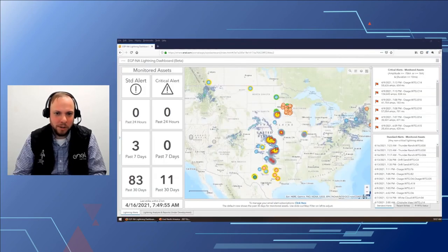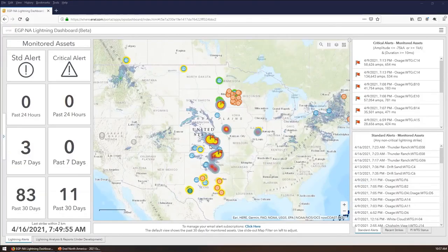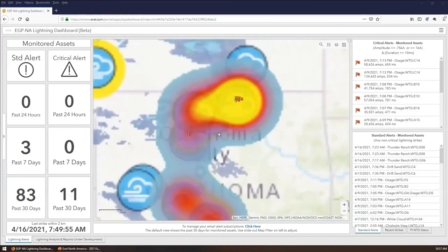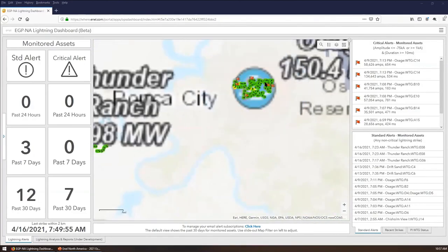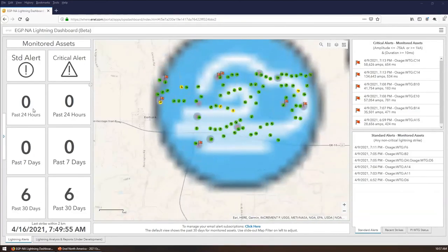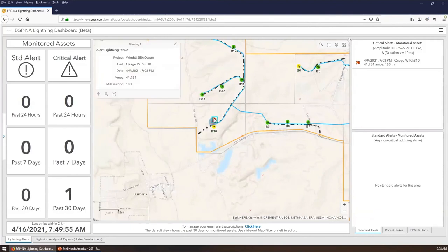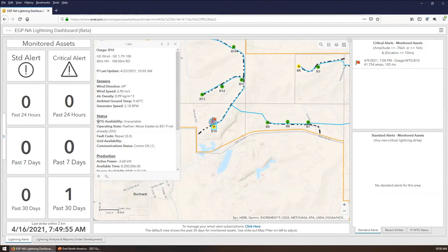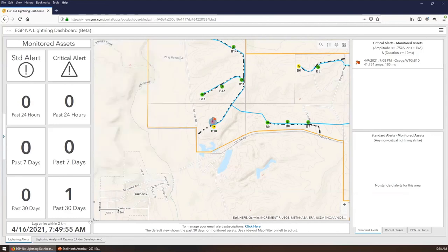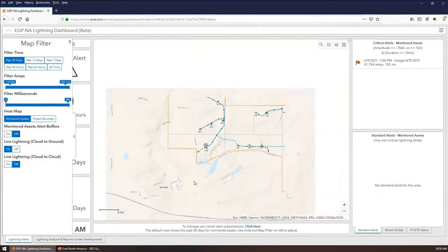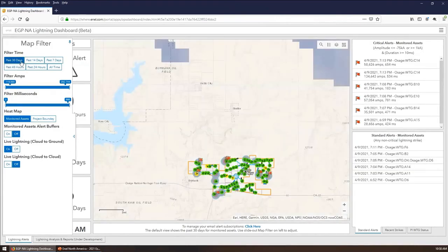Here's a live demonstration of our lightning dashboard. We can see some recent lightning strikes on the right, and I'm going to zoom in on one of those plants to show how this all works. Here's our Osage wind farm, and we can see it did have a couple of recent critical lightning strikes. In this example, we can see this particular strike took place on the ninth and that this turbine is currently down for maintenance and repairs. So in one interface, a lot of actionable information is readily available.